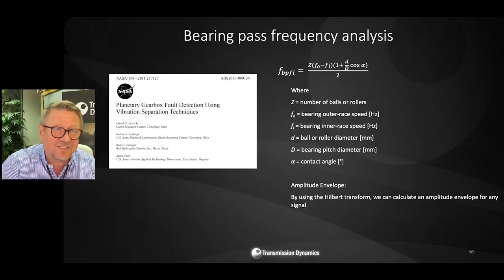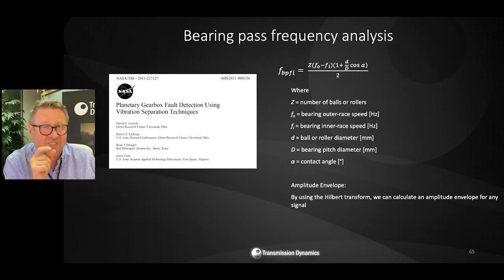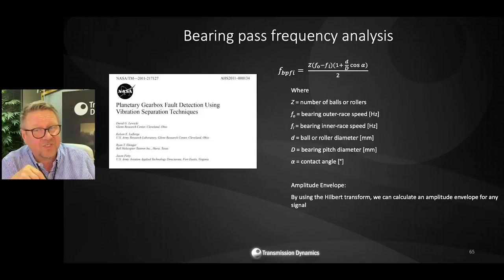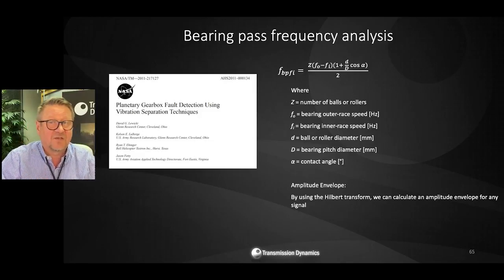We can actually provide the analytics shown in this inset here, where we can use those signals to calculate bearing characteristic frequencies. The equation given on the right hand side allows us to calculate them. So if a feature or a large pit forms on the rolling elements, we can see the frequency of that event. When it forms on the inner or outer race, we can also provide a very accurate frequency of that feature happening.